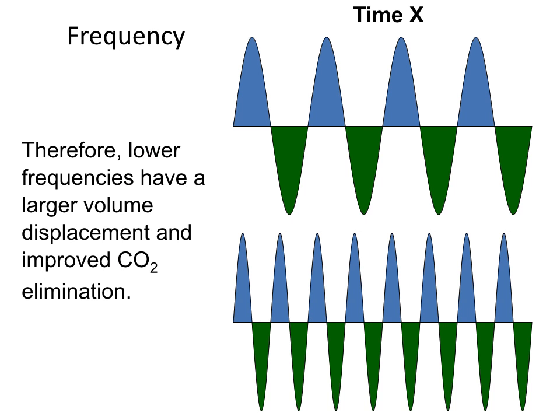Turns out, as you saw, this is the reason for it, so I won't belabor it, but by having slower frequency, there is more time for gas, there's more net volume that's displaced for any given amplitude at the lower frequency. At higher frequencies, tidal volume goes down. When tidal volume goes up, CO2 goes down, of course. And the effect of tidal volume overrides the effect of frequency because it's tidal volume squared, and therefore everybody knows this relationship. When you go down on your frequency on the oscillator, CO2 will drop, opposite of what you normally see with conventional ventilation. You don't see this phenomenon with the jet, because with the jet the I time stays the same.